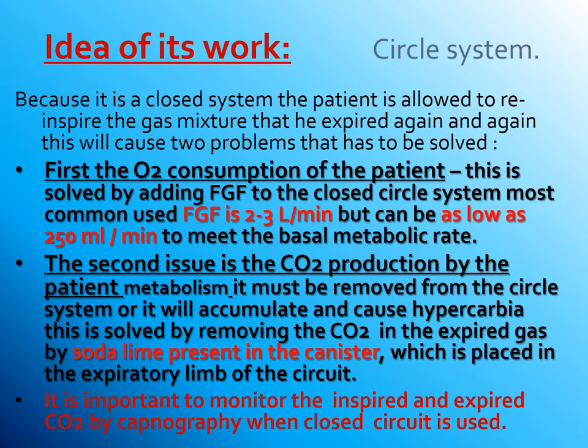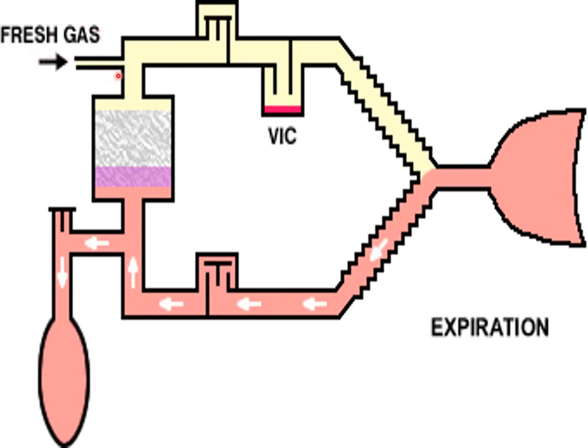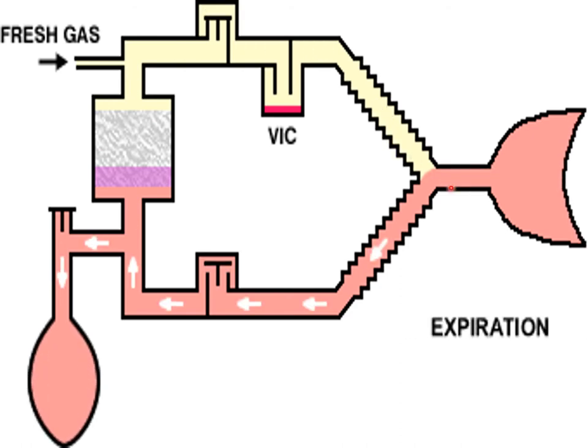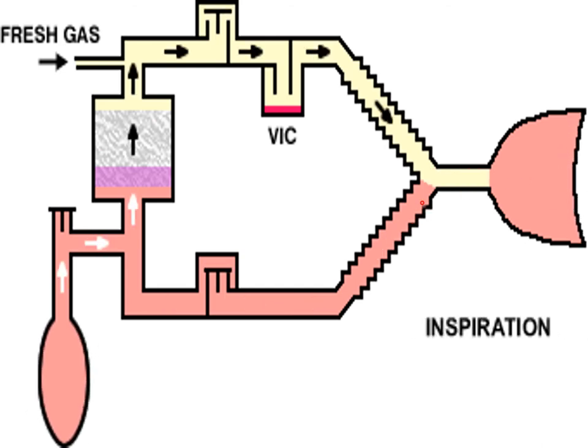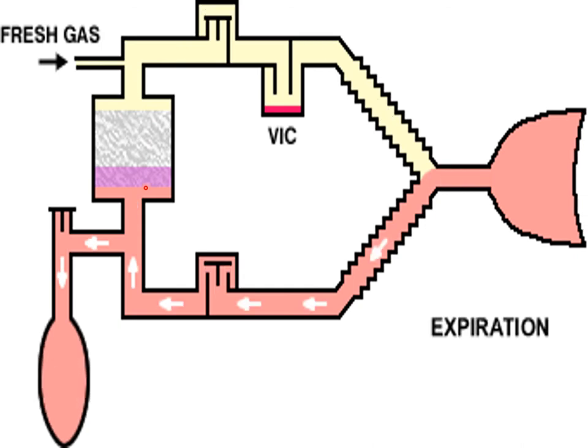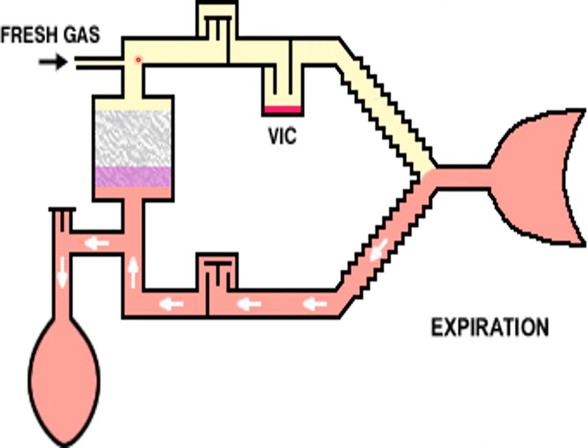It is important to monitor inspired and expired carbon dioxide by capnography when a closed circuit is used. This diagram shows the principal work of the closed system. Fresh gas flows through the corrugated inspiratory tube to the patient. The patient produces carbon dioxide in the expired air, shown in pink, which flows unidirectionally to the soda lime canister where carbon dioxide is extracted, and that gas is pushed through to the inspiratory limb of the circle.